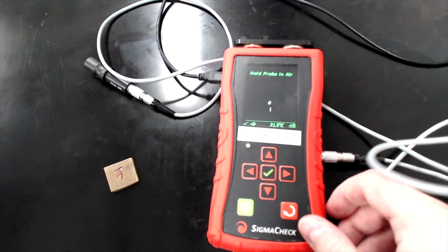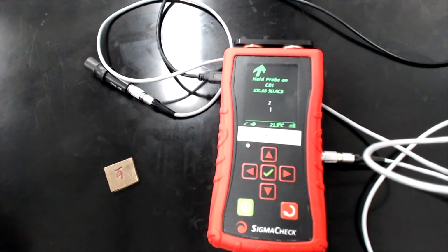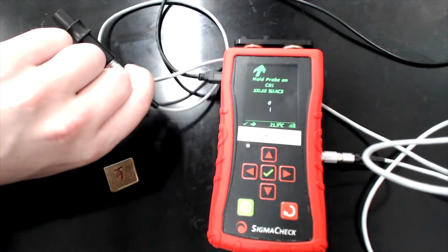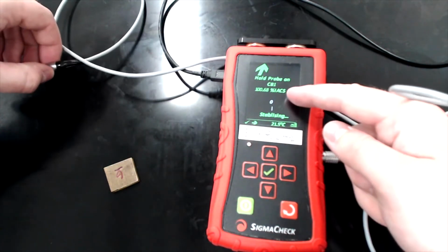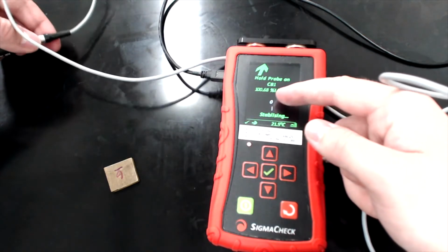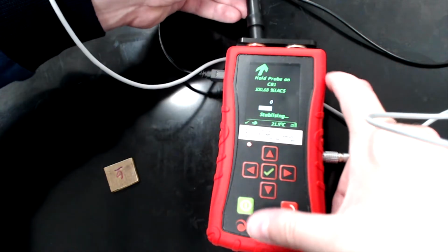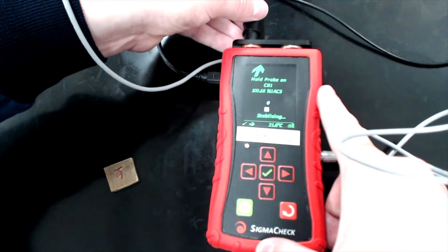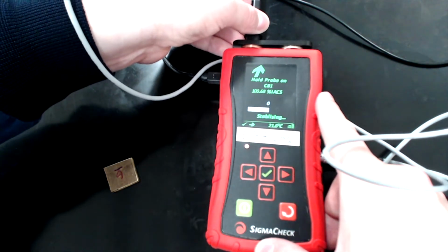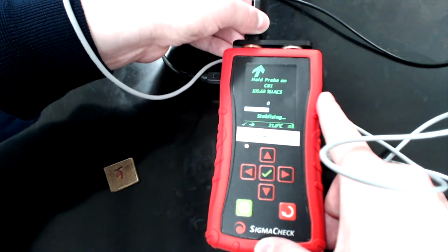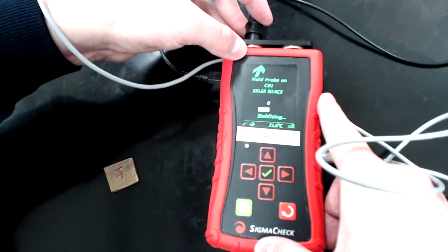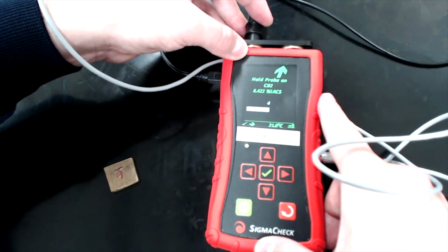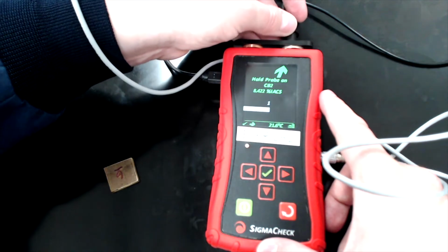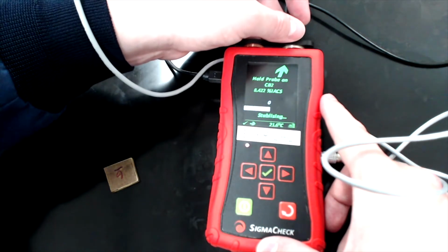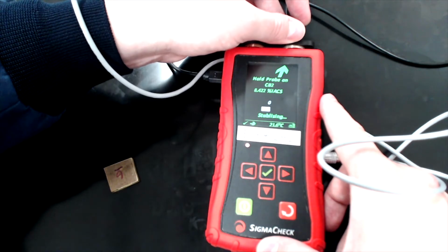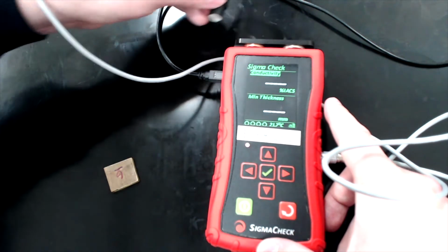This will start the calibration. And it walks you through how to do this test. So that first one says hold it in air, so all I did was just, it was over here and it was ready to go. Now it says put the probe on the 100.68 value sample, and so that's the one over here. And so it has a little slot for it to go, and you just hold it flat, and you'll start to see that it holds steady. If you're not holding it steady, it will move around. So you want to make sure you hold it very steady. Now it says go to the other one, the second calibration standard, and you hold it on there. That's the 8.422. And I'll hold it, and it's ready to go.